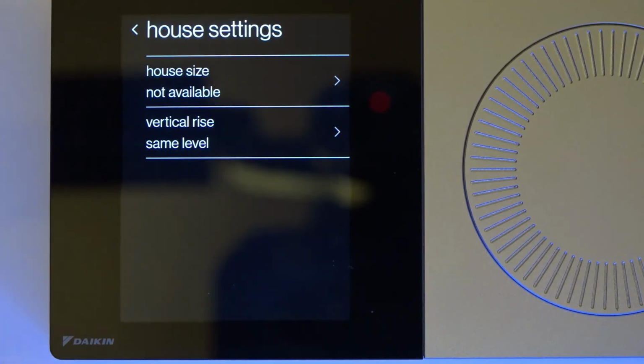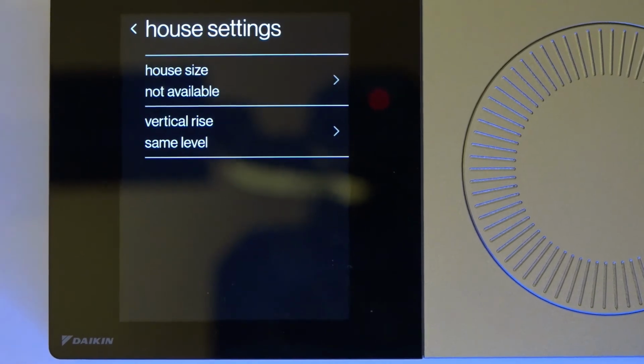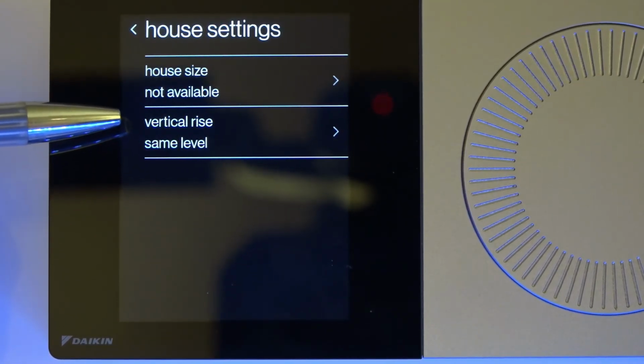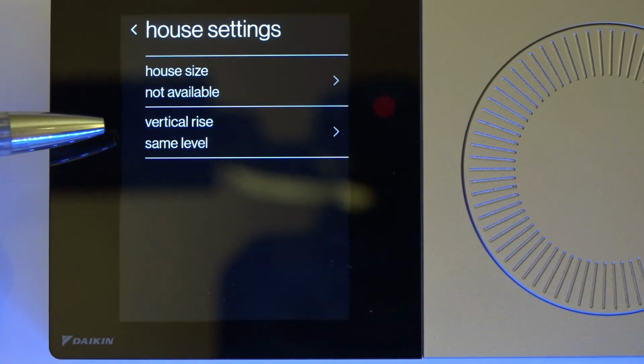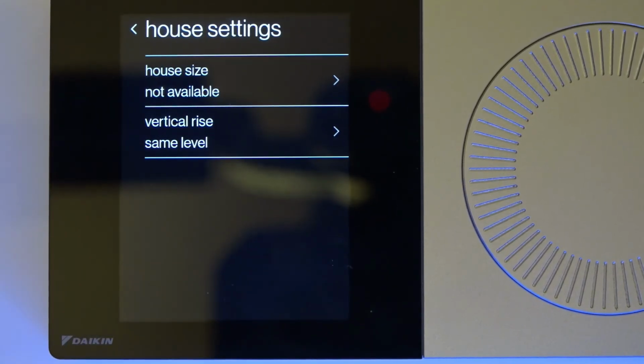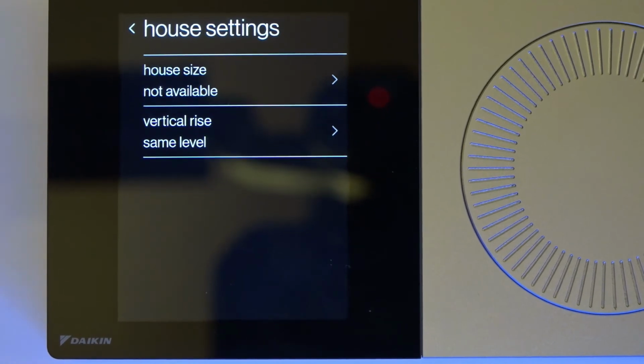And then house settings. I need to be able to tell here, is the condenser higher than the indoor unit, lower than the indoor unit, or at the same level. This system has an oil return mode in it. Every so often it'll slow the fan speed down. It's bumping liquid through the system to be able to grab pockets of oil in the sealed system and return it back to the accumulator so it can feed it back to the compressor. Telling how the compressor is sitting in relationship to the indoor air handler changes that algorithm and how it's going to work.